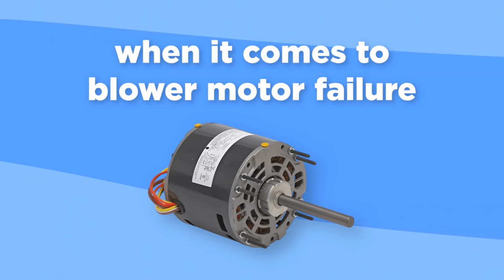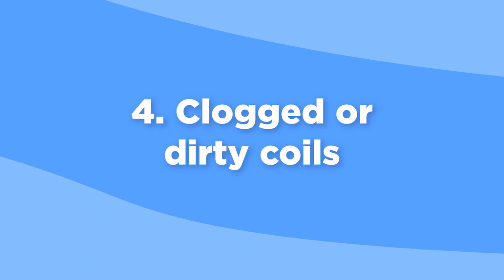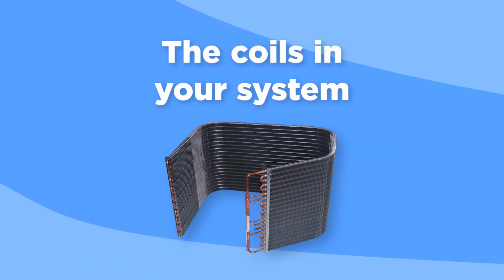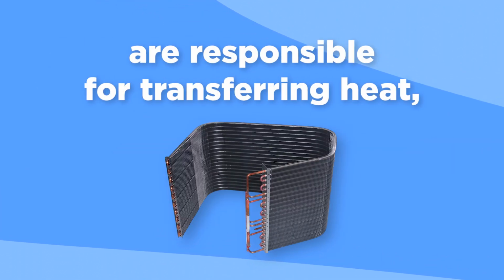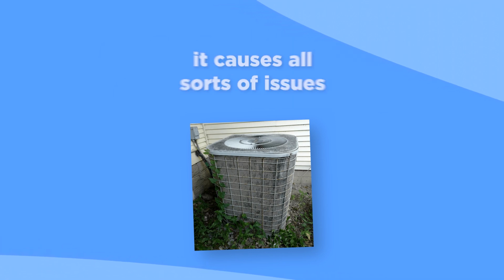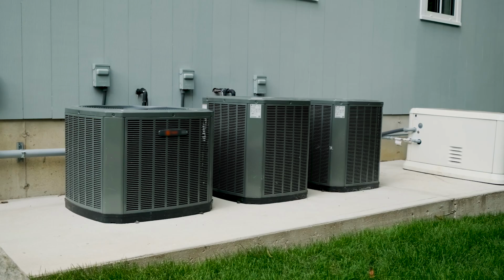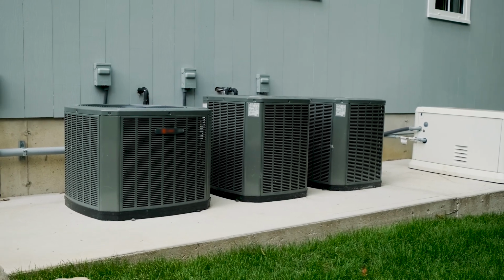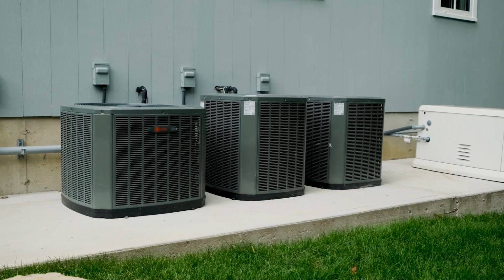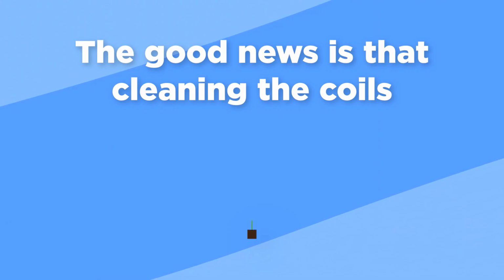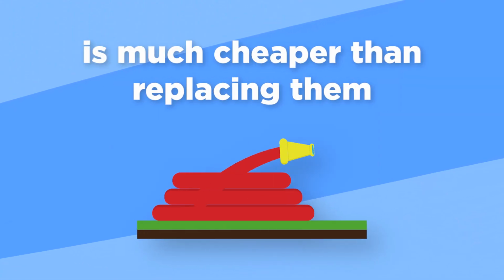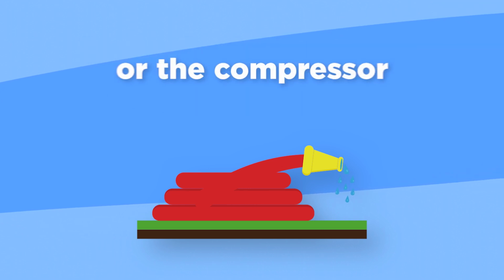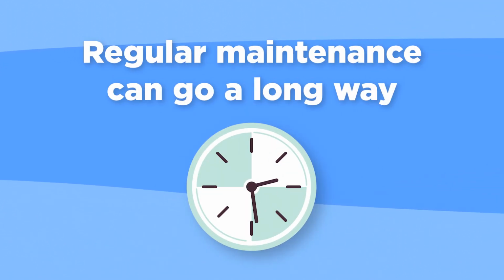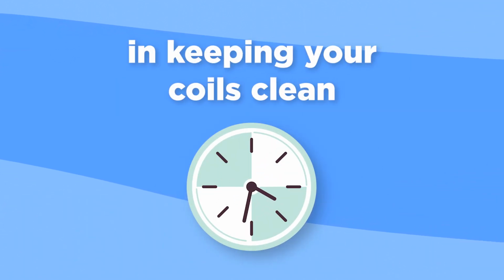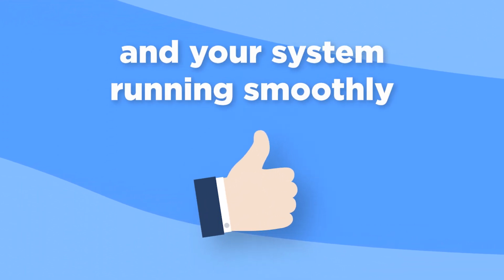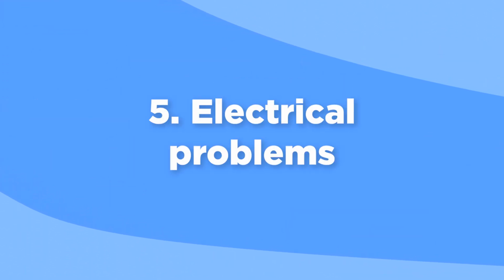Clogged or dirty coils are also a big problem. The coils in your system are responsible for transferring heat, and when they get dirty or clogged, it causes all sorts of issues. Not only does it make your system less efficient, but it can also lead to overheating and even compressor failure. The good news is that cleaning the coils is much cheaper than replacing them, or the compressor. Regular maintenance can go a long way in keeping your coils clean and your system running smoothly. Finally, there are electrical problems.